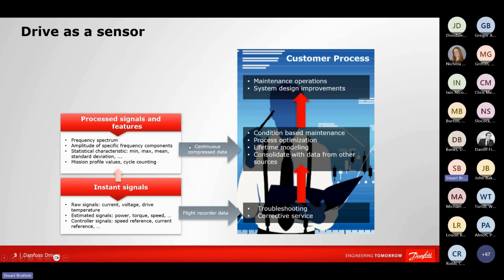But if we process this data in some way in the drive, so for example, if we're recording current that's going out to a motor, rather than looking at the RMS value of that current or the peak values, maybe the drive can actually analyze the frequency spectrum of the current. Are the components that make up that current, have they changed in some way? Or we can look at the amplitudes of specific frequency components. Again, detect, are those changing in some way?